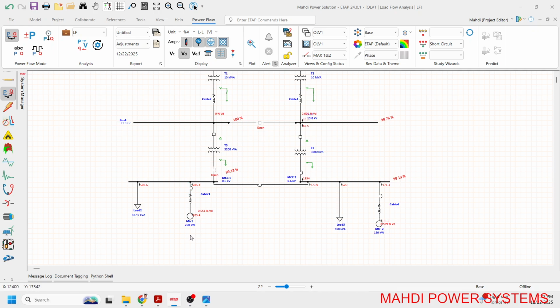In this series, I'm going to coordinate an electrical system starting at the 600 volt level, this bus. I'll begin at the motor level, then move upstream to the motor breakers, here, and then coupler and both incomings, and later medium voltage protection.